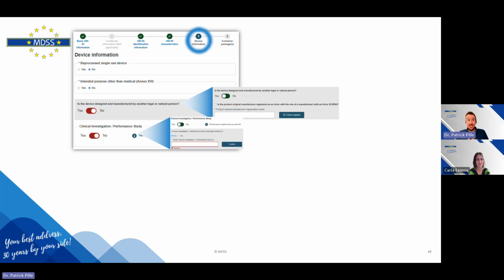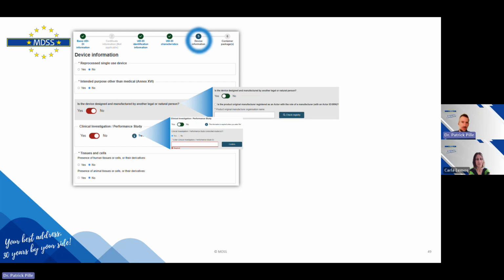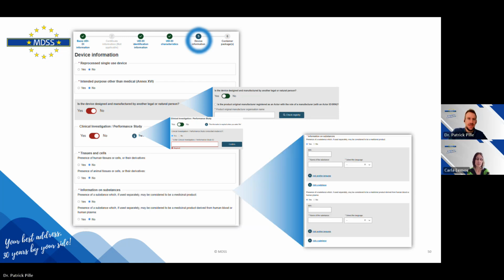If the device was subject to a clinical investigation, or performance studies for IVD devices, indicate it here and indicate the identifier of the study. The presence of tissues and cells of human or animal origin is to be indicated; usually that's straightforward. And if there are substances that, if they were not included in a device, would fall under a medicinal product, this has to be indicated here. And if those substances are present in the device, the international non-proprietary name has to be indicated, so the name of the active substance.